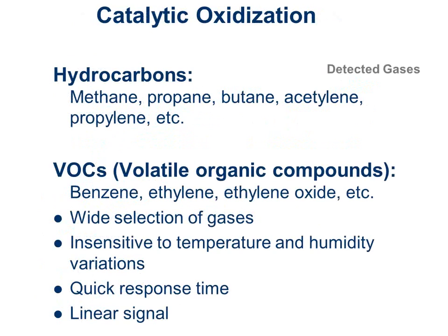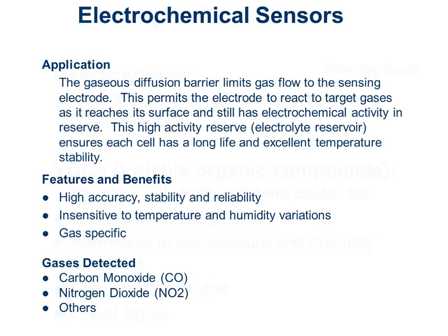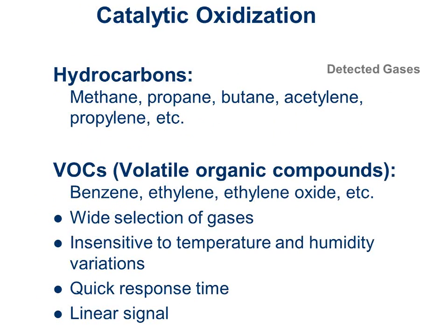You do need to get the sensor to be specific to the exact gas you want, whereas with catalytic oxidation sensors, you can have one sensor that covers multiple gases. There's a pro and con to that. The pro is I can buy one sensor and cover my bases for four or five different things. The bad news is I can't tell you which thing is the problem in your space. Having a more specific sensor, I can say your problem is carbon monoxide because I'm measuring only for that, versus some combination of things.